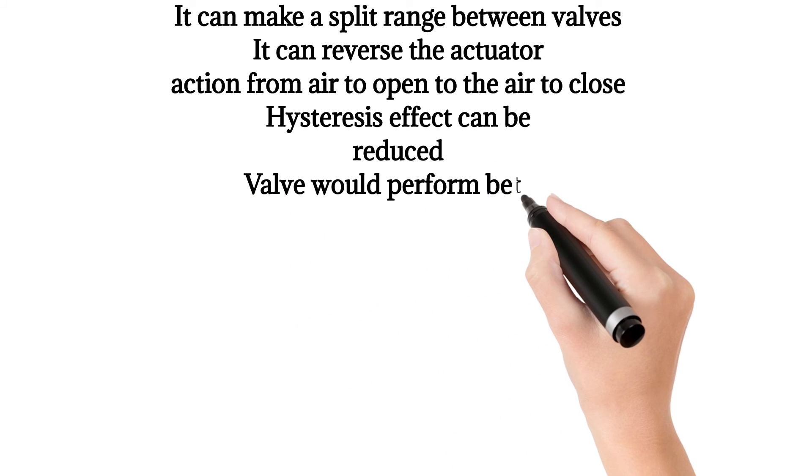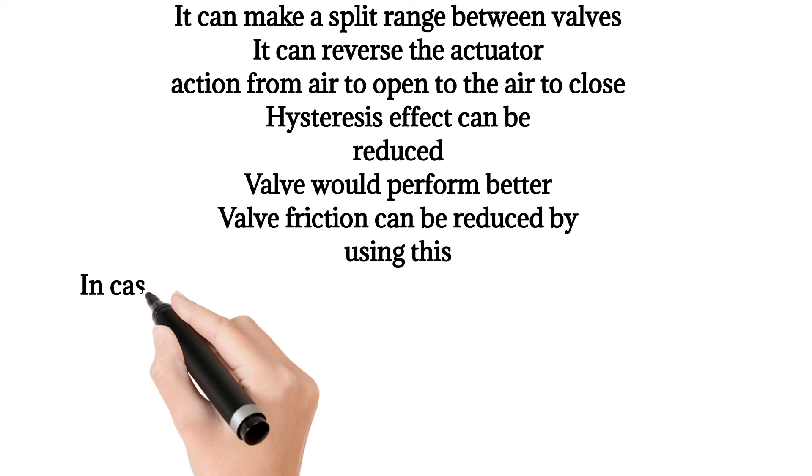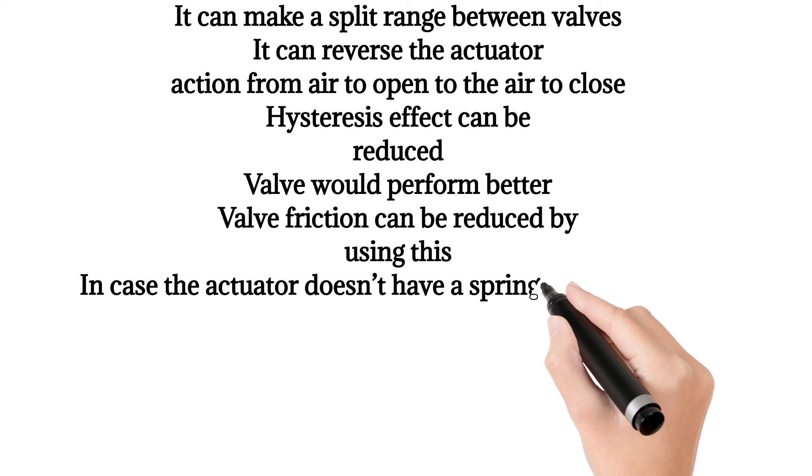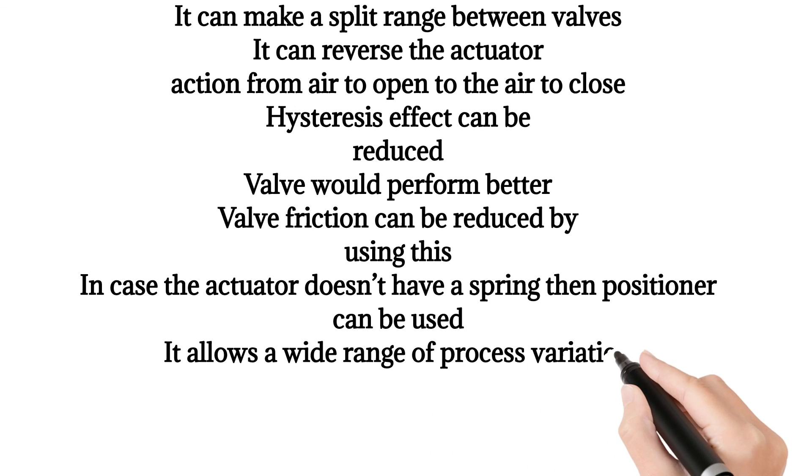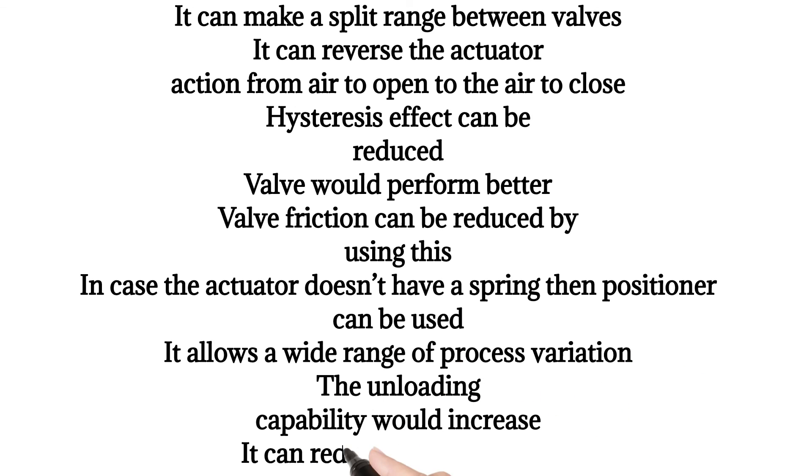Valve would perform better. Valve friction can be reduced by using this. In case the actuator doesn't have a spring, then positioner can be used. It allows a wide range of process variation. The unloading capability would increase. It can reduce actuator sizing.